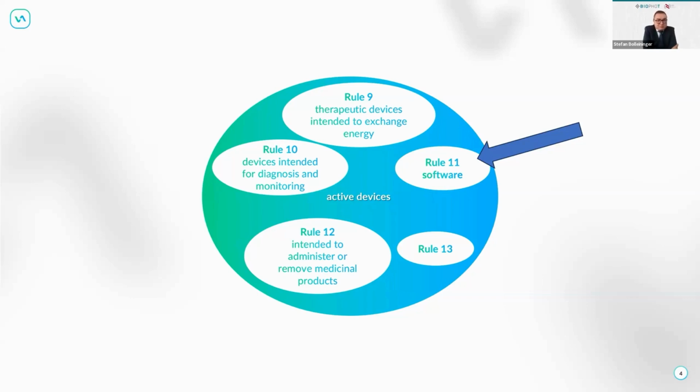So prediction, prognosis, all of those which are not directly in relation with the illness, those can be class 1 devices. Especially if it's not talking about the patient, about the physician, but more on the patient side, then it will be a class 1 medical device. That is the current rule set.